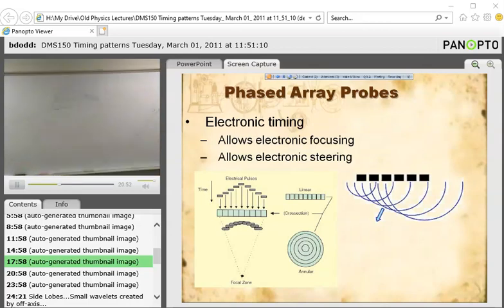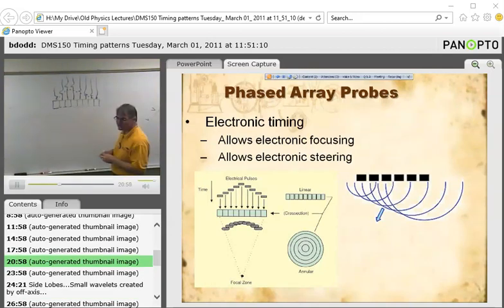Now, is this done by the same crystal or is it a different row of crystals? No, same crystal. And every time you send out a pulse, you have to sit and listen for the entire depth of your image. So if I'm down here imaging at 10 centimeters, even though I want this focus at 2 centimeters, I have to wait until it travels down here and back, which is 130 microseconds, before I send out this next pulse. And this one I have to wait 130 microseconds before sending out this pulse. So every time, it's just like creating a whole new scan line each time.